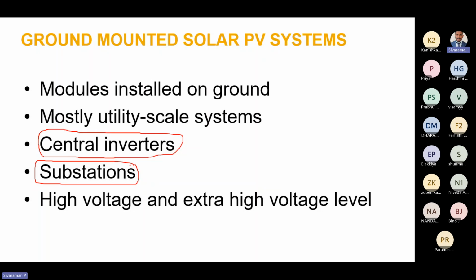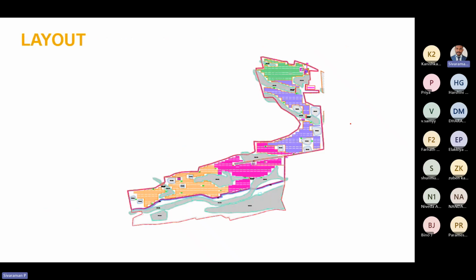On the other hand, most ground mounted solar PV installations require a substation, and a high voltage and extra high voltage transmission line to interconnect the solar PV system to the existing power grid. It will be at high voltage level up to 110 kV or 132 kV, and extra high voltage starting from 220 or 230 kV level to 400 kV voltage level, right? So this is the general overview of the ground mounted solar PV system.